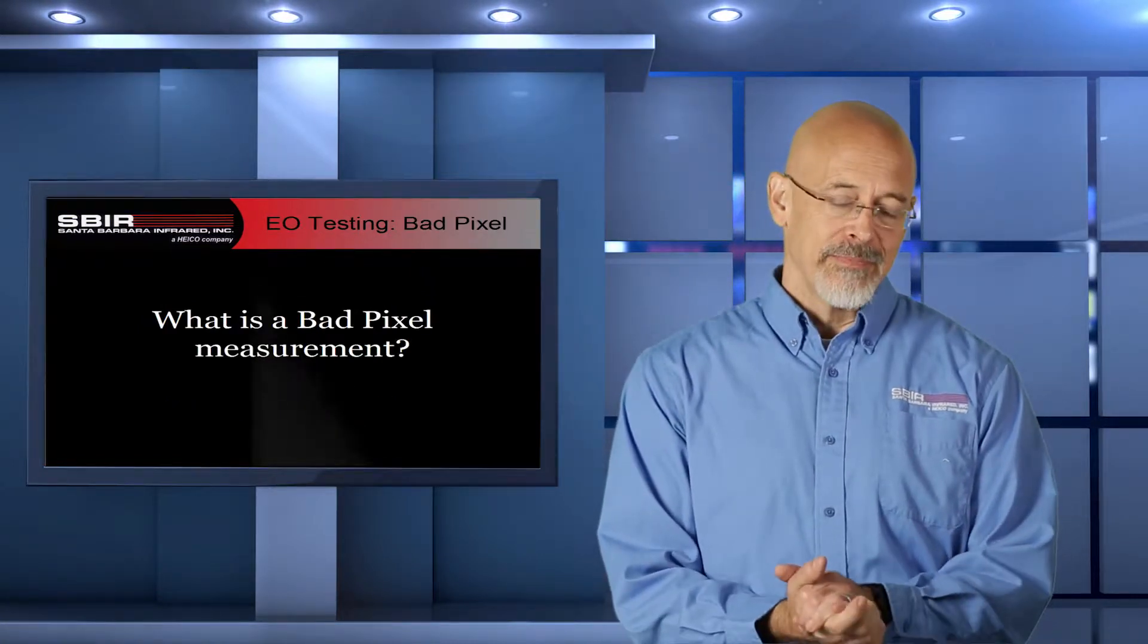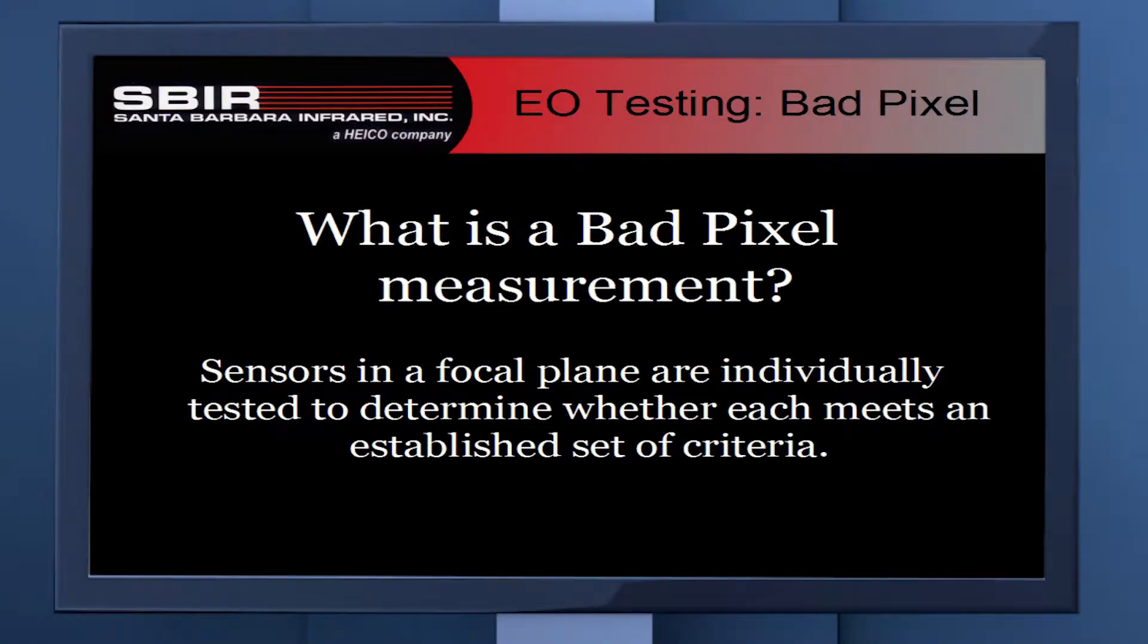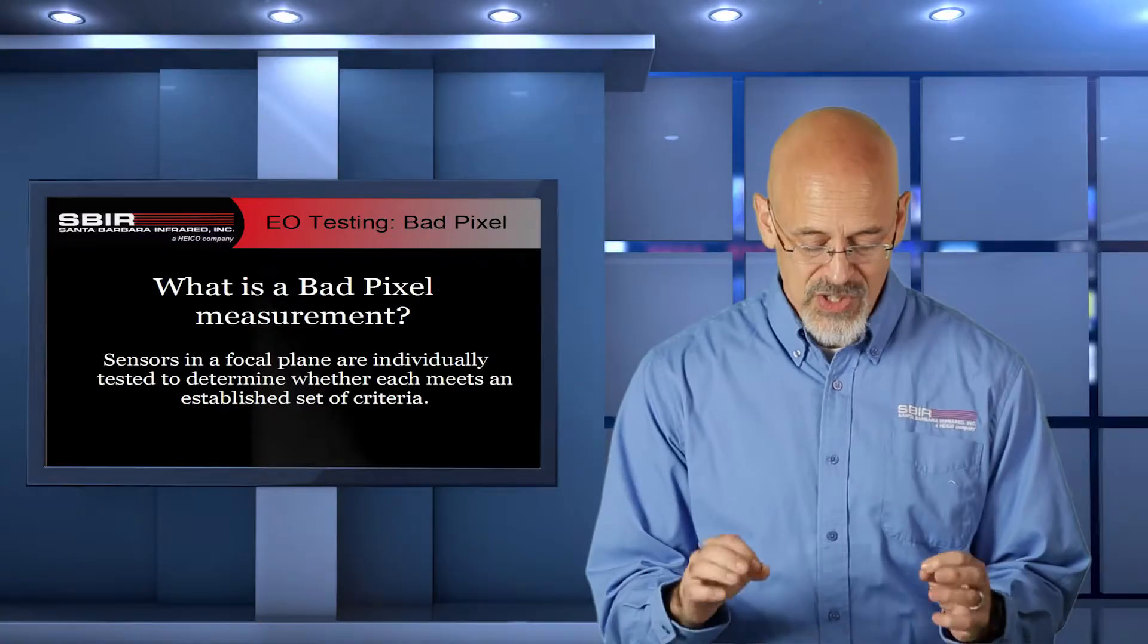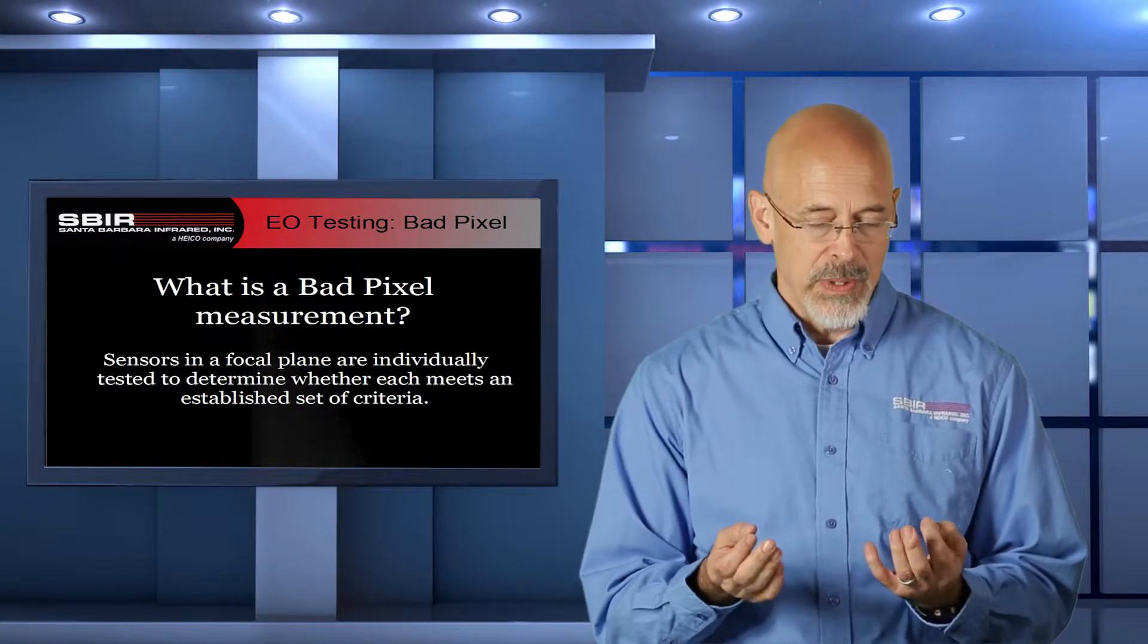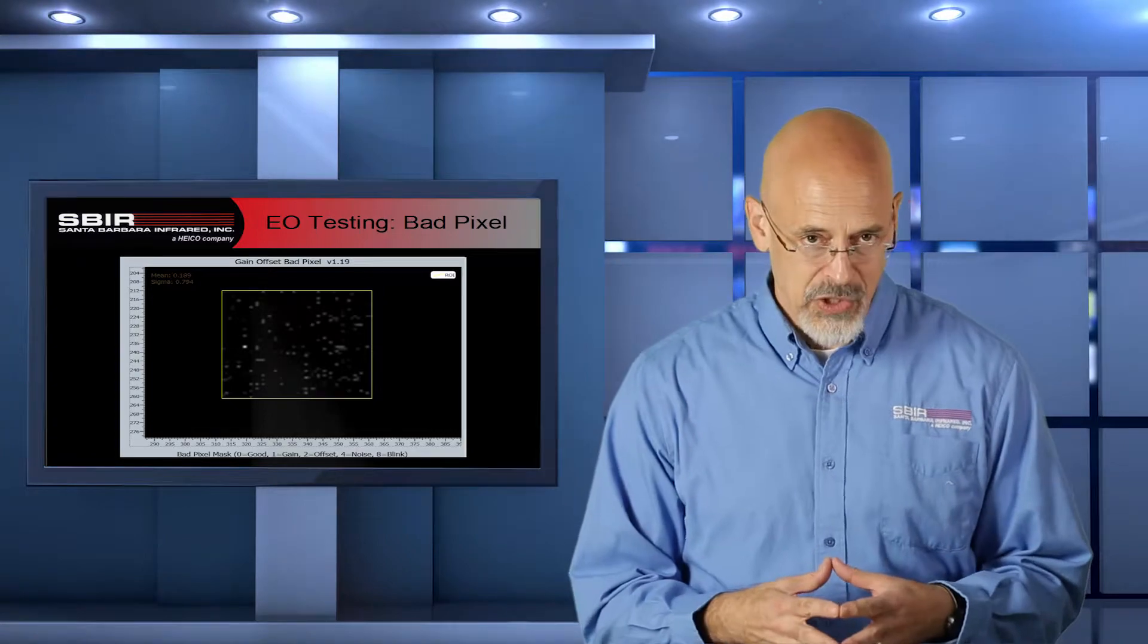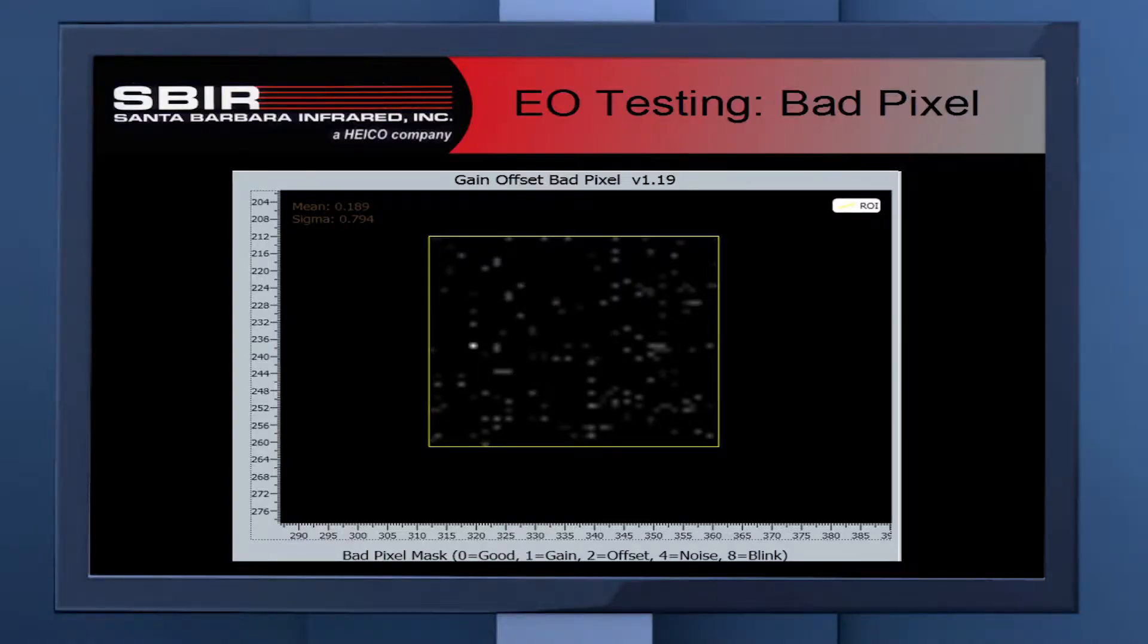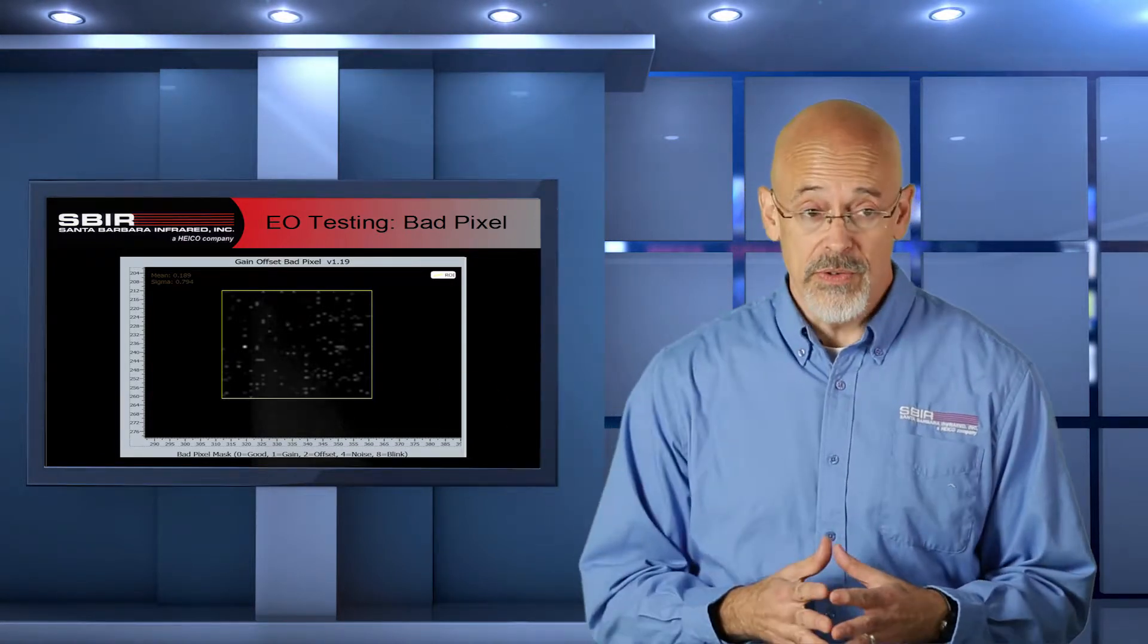So, what is a bad pixel measurement? What we're trying to determine is whether a focal plane, the sensor itself, is acceptable, whether it passes our set of criteria. We've established a set of criteria for every pixel in that focal plane, and we're going to analyze those pixels to determine whether they fit within our criteria. This would be a standard pixel map, a bad pixel map, where we've identified all the bad pixels. This would be a map of those bad pixels in the overall field of view of the camera, or at least in the range of interest.